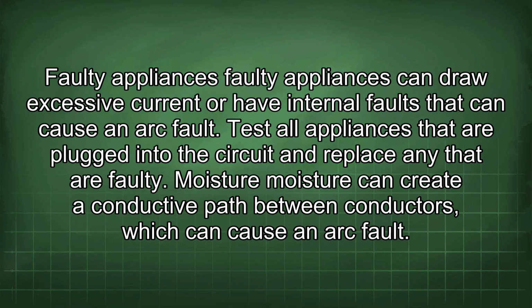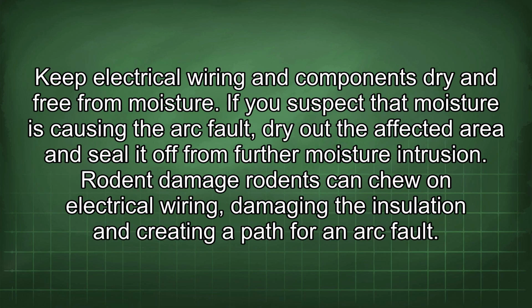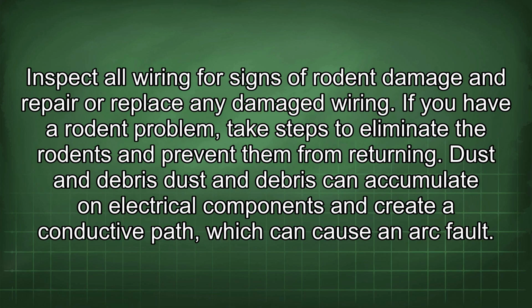Moisture. Moisture can create a conductive path between conductors, which can cause an arc fault. Keep electrical wiring and components dry and free from moisture. If you suspect that moisture is causing the arc fault, dry out the affected area and seal it off from further moisture intrusion. Rodent damage. Rodents can chew on electrical wiring, damaging the insulation and creating a path for an arc fault. Inspect all wiring for signs of rodent damage and repair or replace any damaged wiring. If you have a rodent problem, take steps to eliminate the rodents and prevent them from returning.